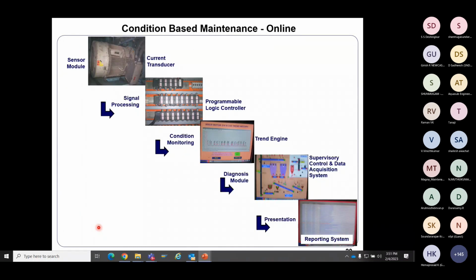So this is an example. If you take a motor, this is online. You have a sensor module. What to sense? Obviously, you can sense the current, the temperature, whatever the case may be. The current transducer feeds the signal into a PLC. The PLC gives SCADA the trend, and it will show what the no load current is and what the full load current is. The diagnostic module will check whether there is an increase or a decrease. Obviously this will give a trigger and a fault alarm in the mimic panel.